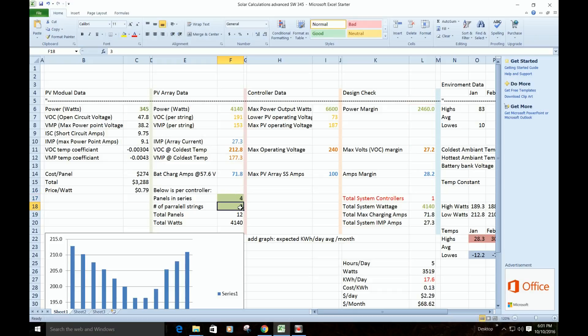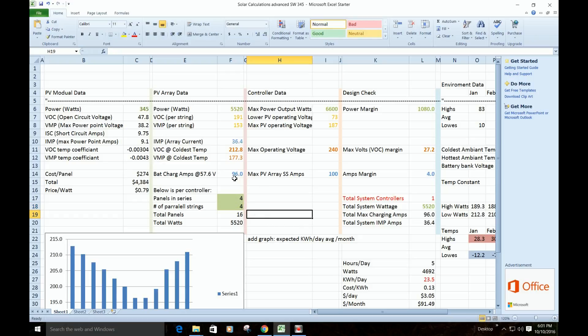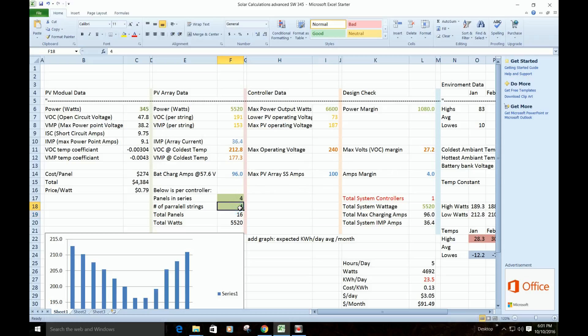Now, the more strings in parallel we put, the higher our current's going to go. So we're getting 96 out of 100, we only got four to spare. Now, you could probably do that, and you're probably never actually going to see 96, but that should be the worst case scenario. I don't know if I want to push it quite that much, so I'm just going to stay down here at three.